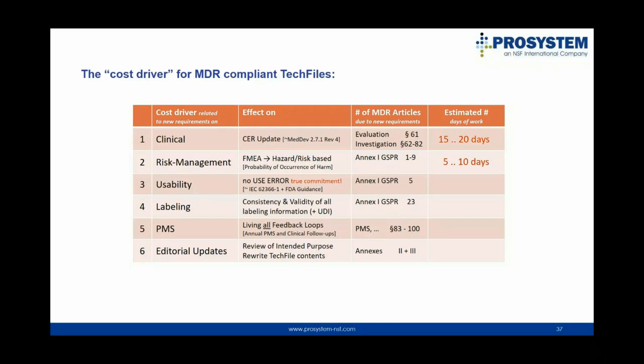If we read the requirements in Annex 1 of the MDR, the new General Safety and Performance Requirements, you can find out that the concept of a failure mode and effect analysis would not be sufficient to meet MDR requirements. The text and the requirements on the risk management systems are clearly defined top-down. Terminology like hazard or hazardous situation is clearly phrased in the letter of the law. And if a medical device has as a backup in an existing risk management file only FMEA documents, this would not be compliant with MDR.